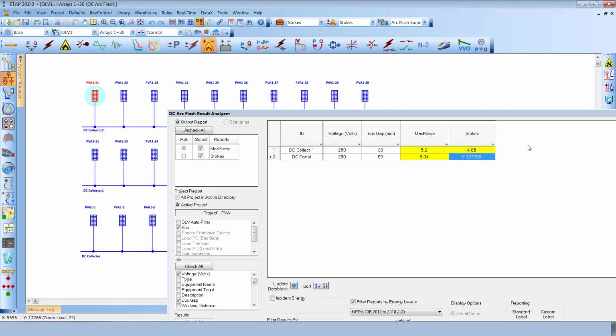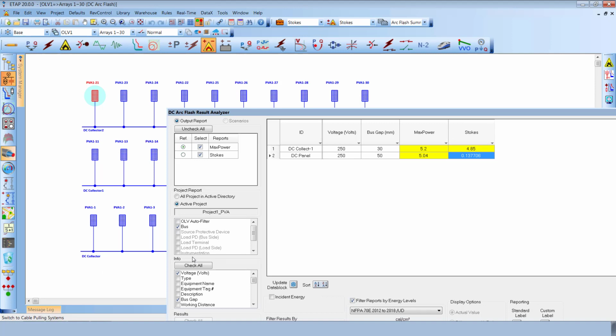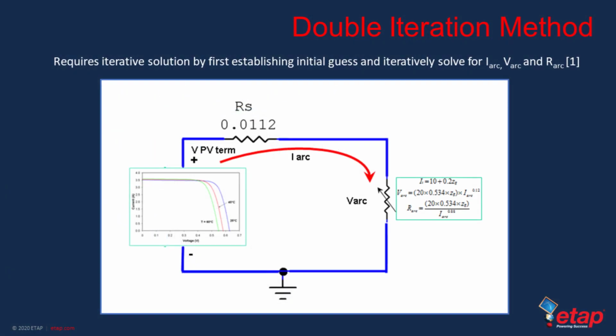is the concept of the double iteration method, which is far more accurate than the actual IBF and the I-arc relation from the maximum power method. In other words, the power released by the arc as a function of the voltage drop across the arc and the current, not based on the actual open circuit voltage of the system and the current. And this voltage drop across the arc in the Stokes method is actually a function of the gap between the conductors that is calculated using the test results performed by Stokes and Oppenlander for copper and aluminum electrodes.